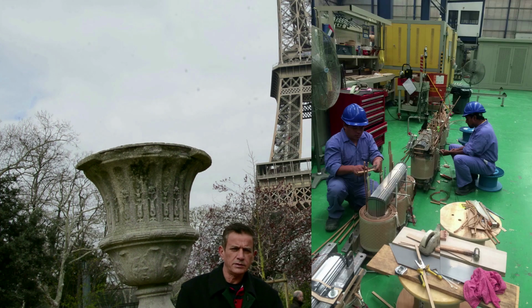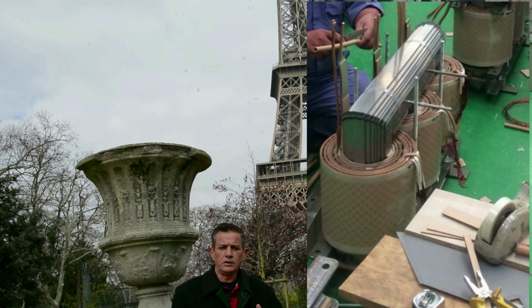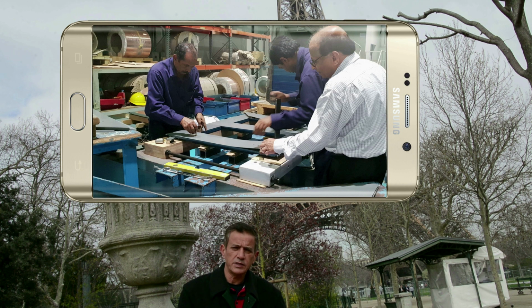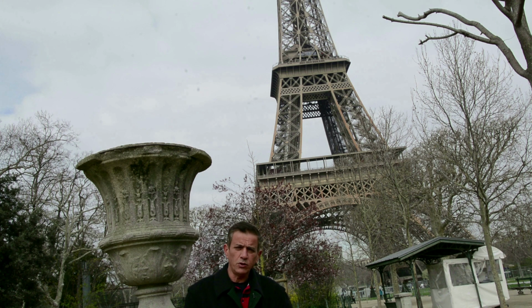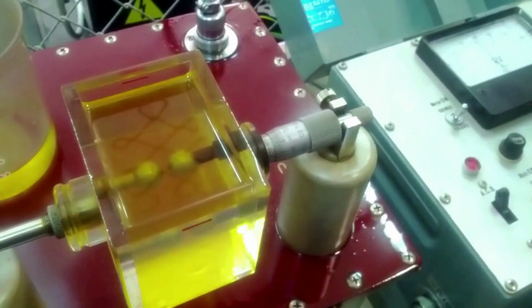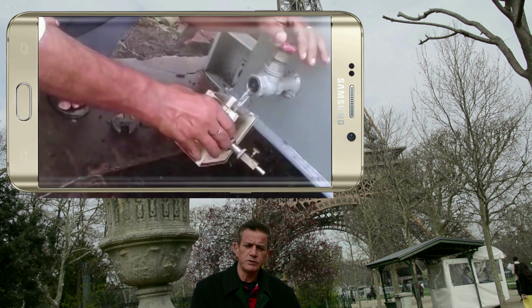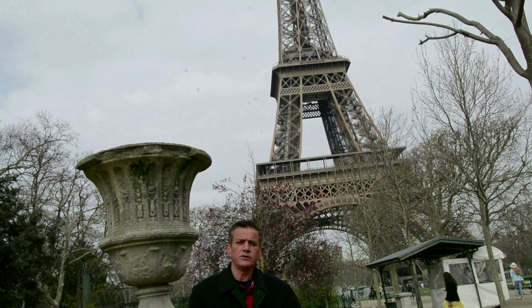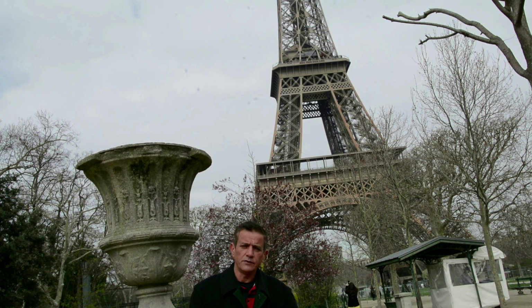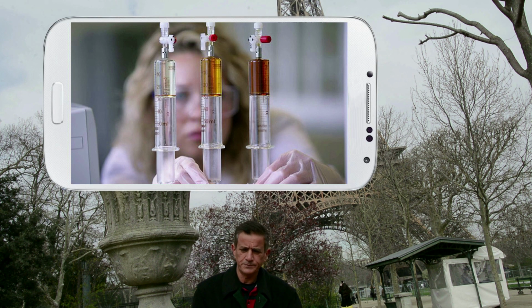Let's take the windings, for example. We can test the winding resistance. We can test the insulation of these windings. For the core, we can test the magnetic balance. For the oil, we can test the breakdown voltage of the oil. We can take a sample from this oil and see the details of the ingredients of the oil. If some other strange particles are there, we can discover them by taking a sample and analyzing it in the laboratory.